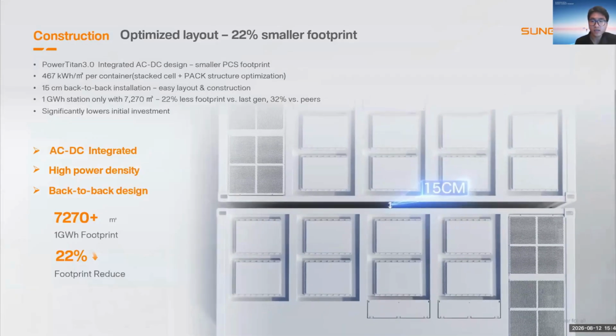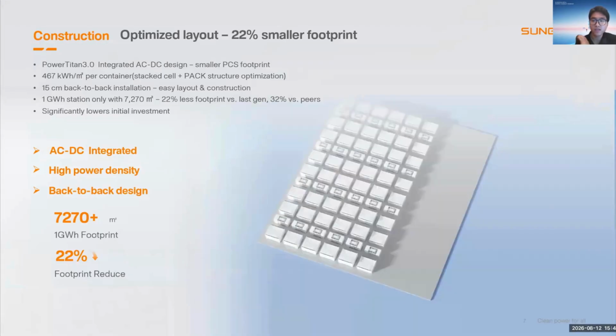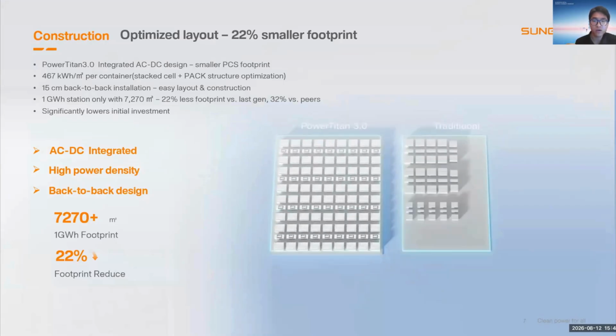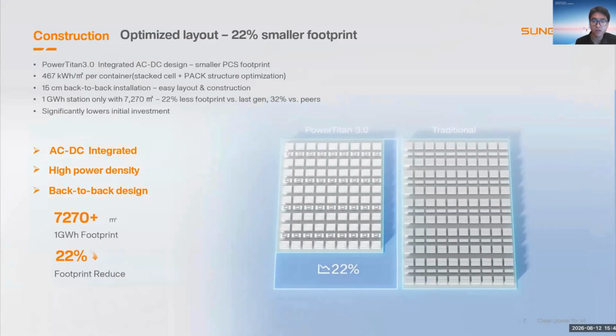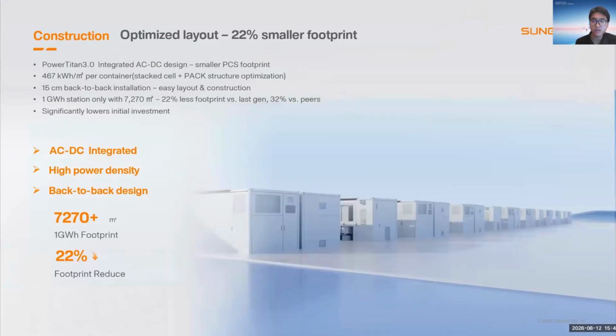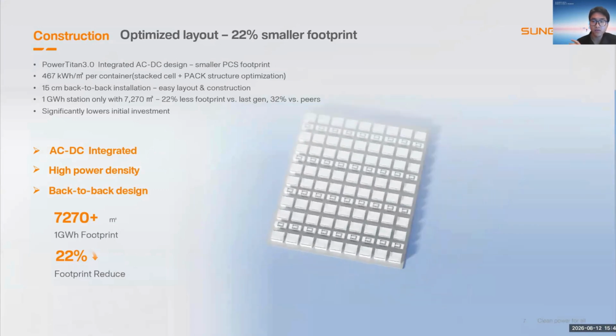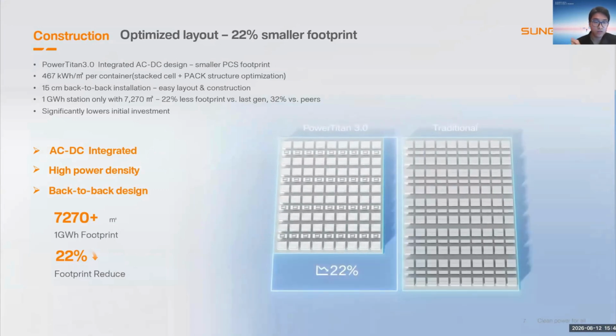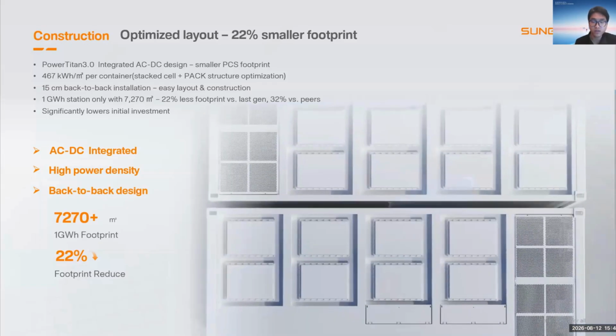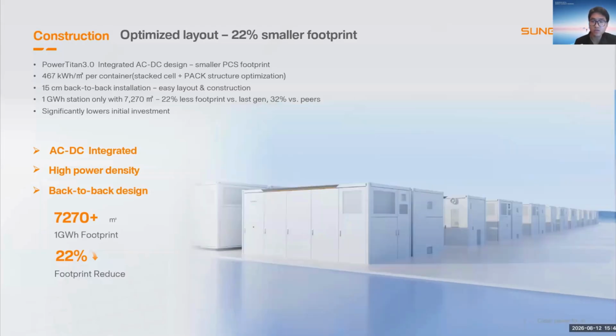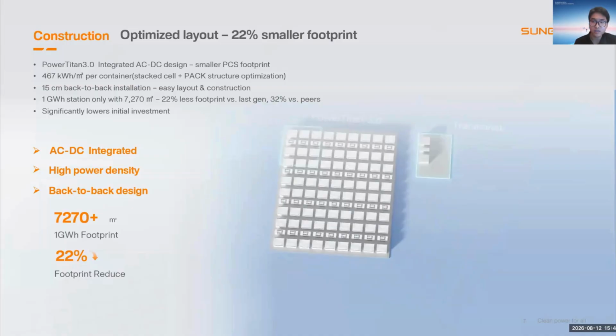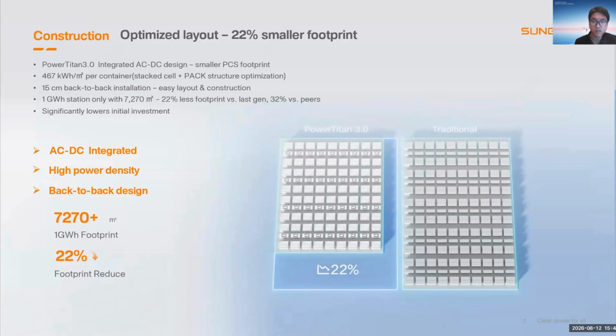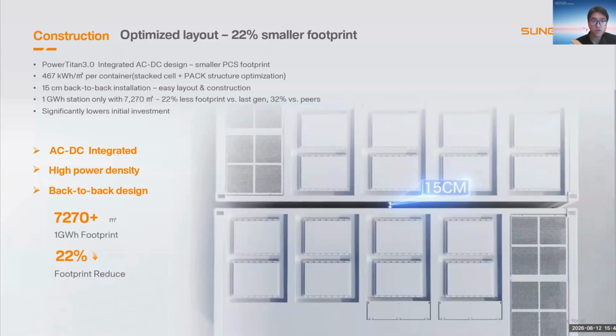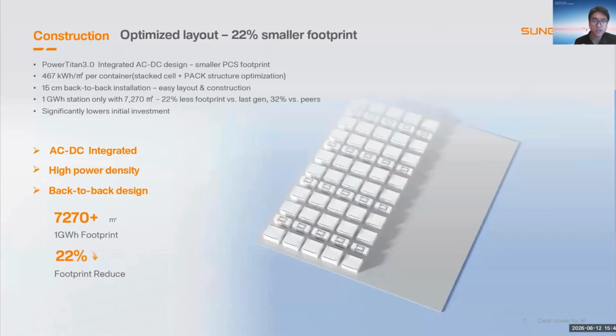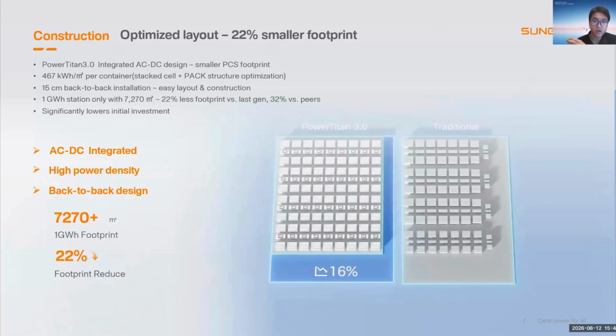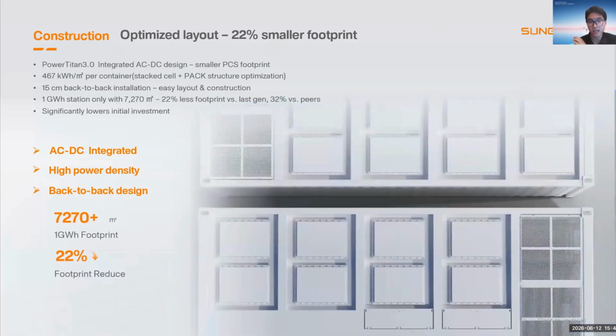And due to the stacking cell technology, the energy density per container can achieve 467 kilowatt-hour per square meter. Also, together with the 15 centimeters back-to-back arrangement design, for each 1 gigawatt-hour power plant, the footprint can be reduced by 22%. As a result, the construction workload is significantly reduced, and the initial investment can be lower in a substantial way. And for sites with land requirements, it can also reduce the land requirement and the land cost.